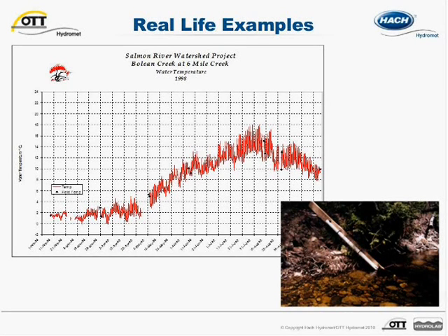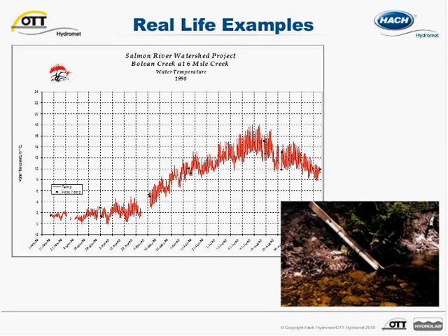This graph shows the temperature data. In this case, a traceable mercury thermometer is brought to the field for QA/QC measurements. Note the frequency of the checks and the relatively close agreement between the QA/QC and the field measurement.